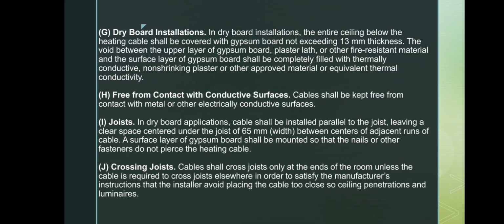Next slide is for dry board ceiling installation. The whole ceiling under the heating cables must be covered with gypsum board no thicker than 13 millimeters. The space between the top layer and bottom layer must be filled completely with non-shrinking, thermally conductive plaster. Cable must not touch any metal or conductive surface. When installed near joists, cable must run parallel to the joists with a 65 millimeter clear spacing centered under each joist. The finishing layer must be installed so that nails or screws do not hit the cable. Cables should only cross joists at the end of the room, unless the manufacturer requires crossing elsewhere to avoid lights or ceiling penetration.